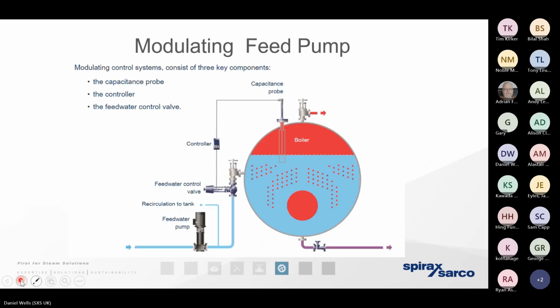So, those modulating feed pumps that we spoke about, another benefit is if you compare a modulating feed pump to an on-off pump: with an on-off pump, the level control may have been set at a very high point for switching off and at a very low point for switching on. We could be bringing a significant mass of water from the hot well in a very short period of time. And if the water in storage in the hot well was at a relatively low temperature, we're going to have a quenching effect. So there's going to be a delay to the point at which we can produce steam. And it also means the ability of the boiler to produce the required mass of steam is going to be further diminished. So if we've got one modulating feed pump in the boiler house supplying 6 boilers, we can be pumping a small mass of very, very high temperature hot water. Whereas if we had an on-off system, then we would require 1 pump per boiler.